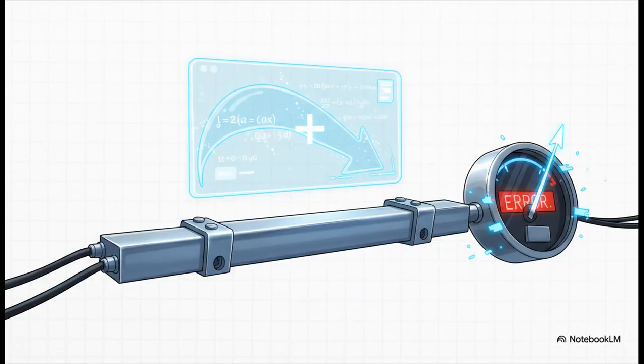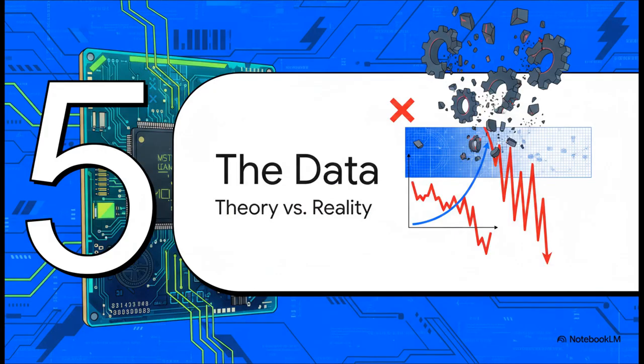So what happens when your model gets this wrong? Well, the model assumes the inverter is always injecting current, even when it isn't. So it mathematically adds this phantom current injection across the network impedance, and the result is a calculated voltage rise at the bus. It's a ghost in the machine, a purely mathematical artifact that creates a result that is physically impossible. Okay, so enough with the theory, let's look at the numbers from the study.